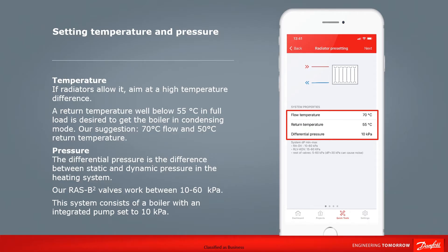Let's set the flow temperature to 70 degrees and the return temperature to 50 degrees. As the RAS B2 valve works between 10 and 60 kilopascal, let's assume that the boiler has an integrated pump set to 10 kilopascal. Once you've entered this information, press next in the top right hand corner to continue.